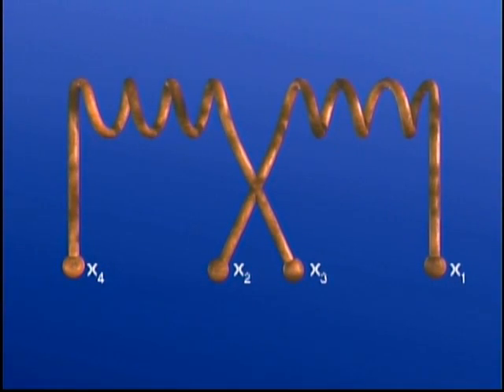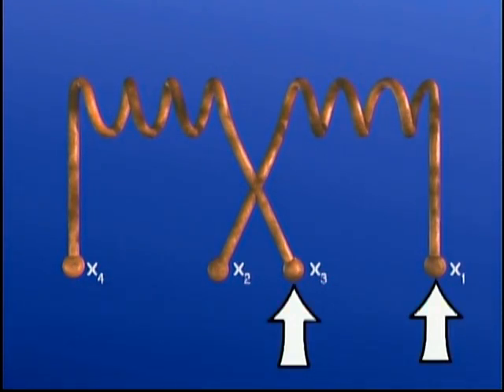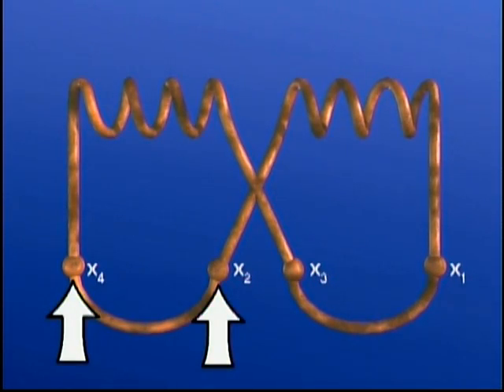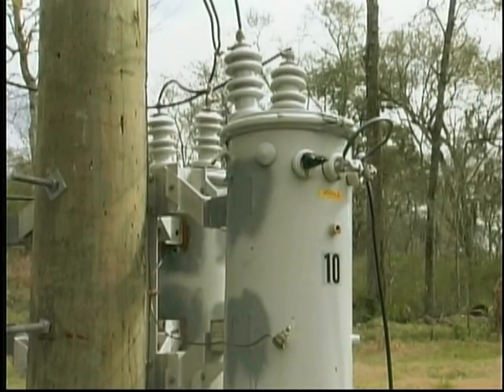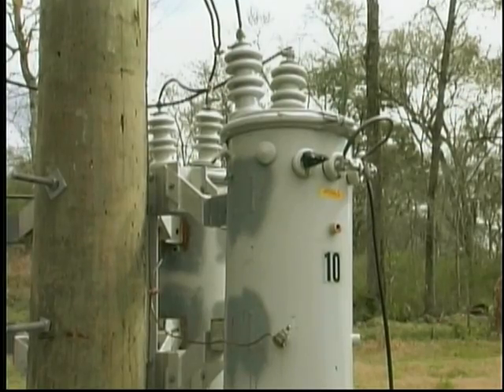For Y connections, the secondary coils are often connected together in parallel. In this case, corresponding ends of each of the two coils are connected inside the transformer at the X1 bushing. The other ends of the coil are connected together at the X2 bushing. When secondary coils are connected in parallel, the X3 bushing is not used.